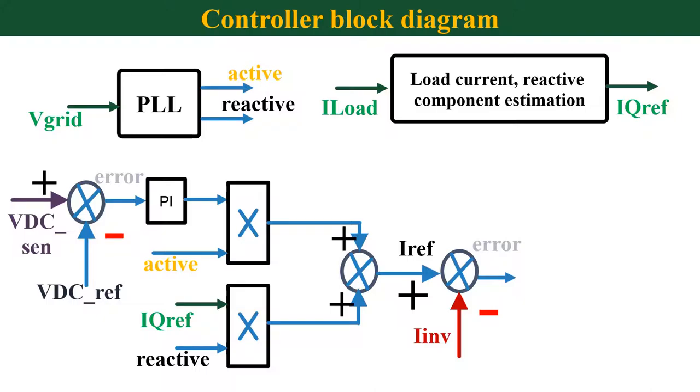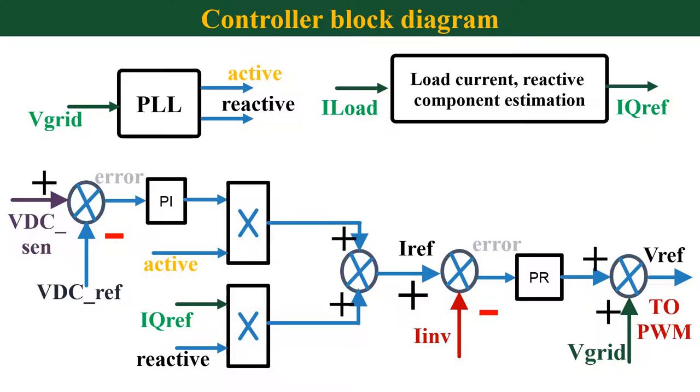Now I will start writing the controller. First, we need to find the error between actual sensed VDC and reference VDC. This error is then fed to a PI controller. The output of PI controller is multiplied with active component generated by the PLL. Now the estimated reactive component in the load current is multiplied with the reactive component generated by the PLL. The output of both the multiplier is then added and that will give the current reference. This current is then compared with the actual inverter current to find the error. This error is then fed to a PR controller. The output of PR controller is then added with the grid voltage. This will give the final reference voltage and this voltage is used for the PWM generation.